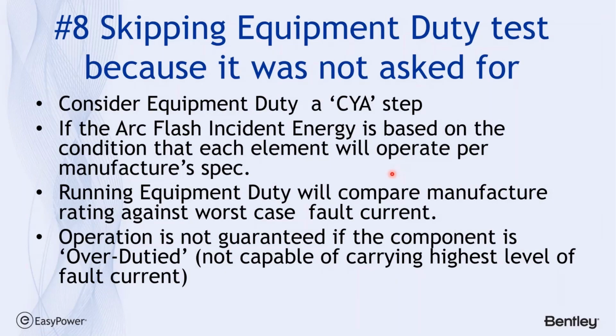Now again, this is another case of trying to limit the cost of the study, where people say, well, no, I don't need to worry about equipment duty tests because the client didn't ask for it. I think you really want to consider this step as a make-sure-you're-not-making-a-mistake step, because arc flash incident energy is based on the condition that each element would operate per the manufacturer's test or spec. And if I haven't verified that, then I'm not on very solid ground when I go to claim that this protective device is going to bring down the incident energy for somebody working downstream.